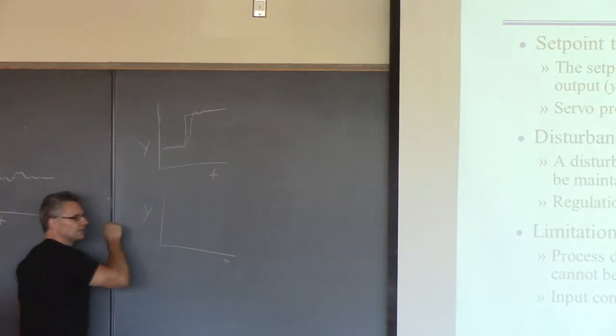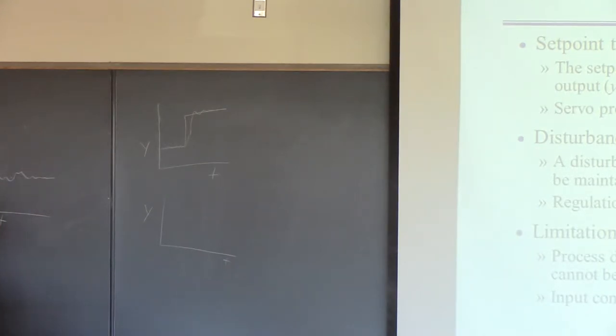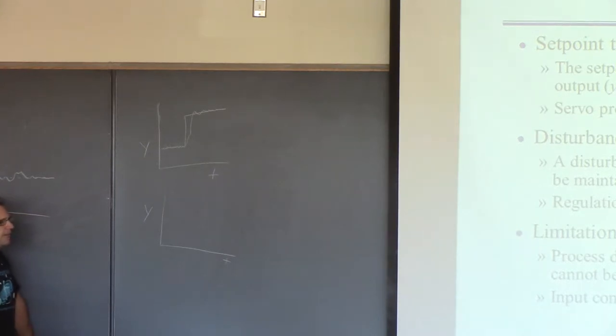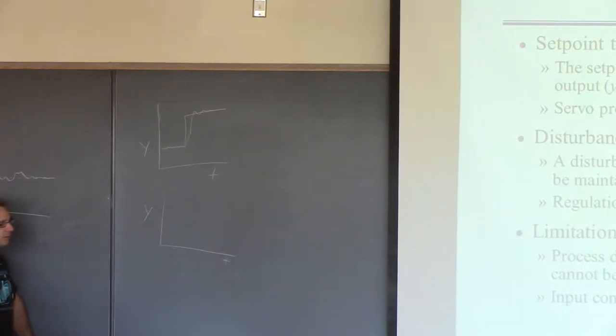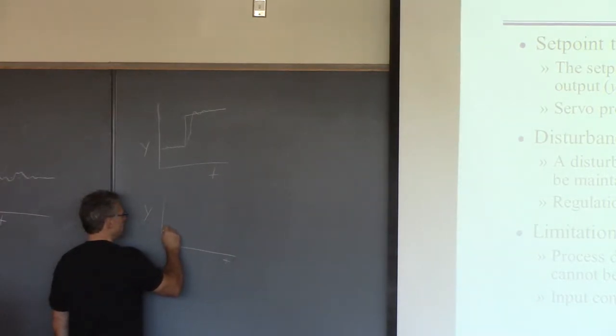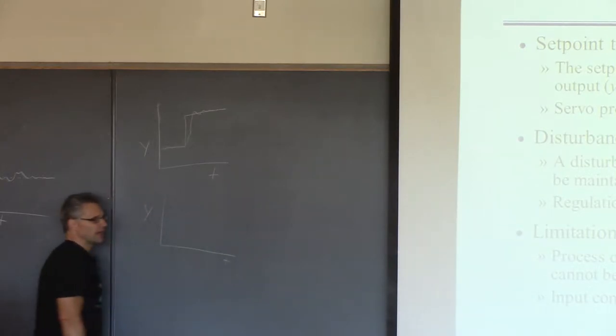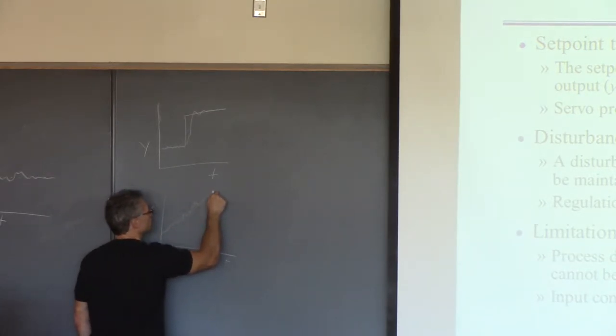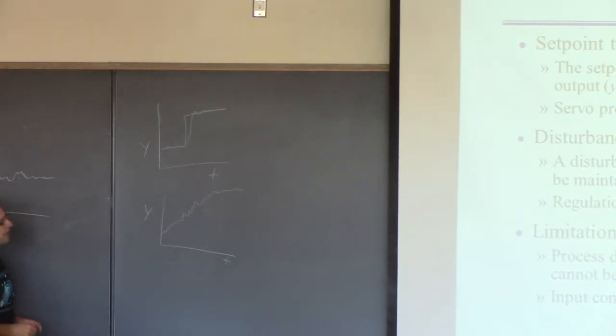In batch processes, like batch chemical reactors, you typically operate with a time-varying policy — the temperature you want changes over time. You can calculate the best temperature trajectory to maximize yield. So if you're in a batch process, you might have some predetermined temperature profile that you're trying to track. This has been pre-calculated, and the controller's job is to keep the temperature near this predetermined set point. Both of those are set point tracking problems.